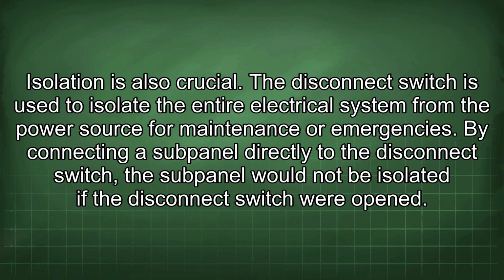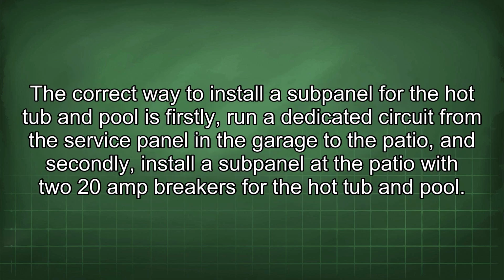Isolation is also crucial. The disconnect switch is used to isolate the entire electrical system from the power source for maintenance or emergencies. By connecting a subpanel directly to the disconnect switch, the subpanel would not be isolated if the disconnect switch were opened.